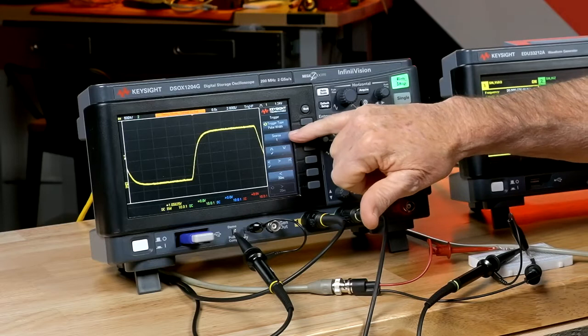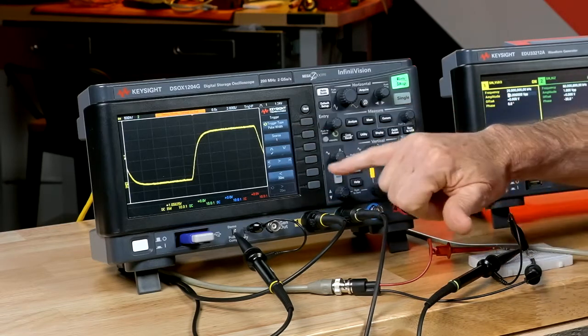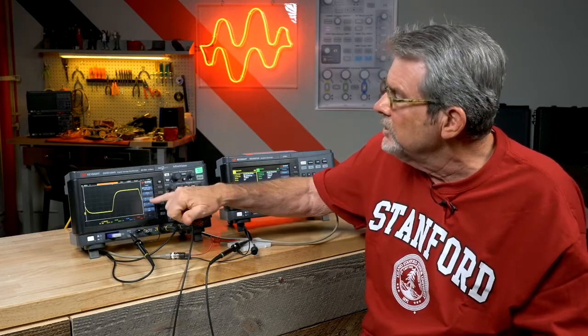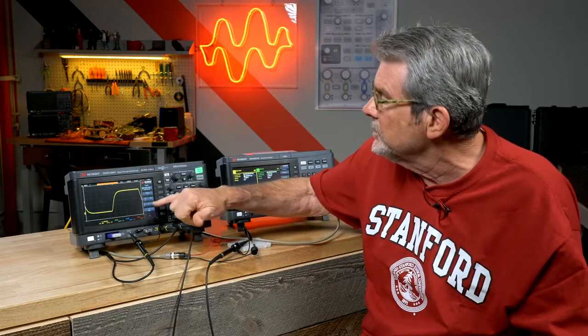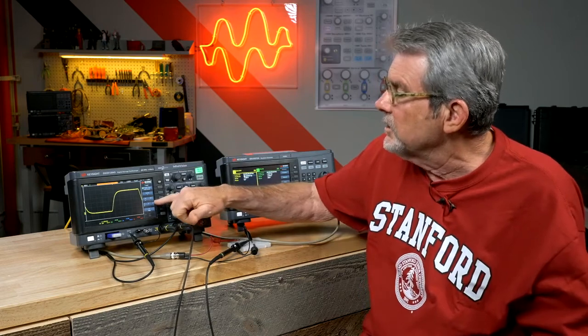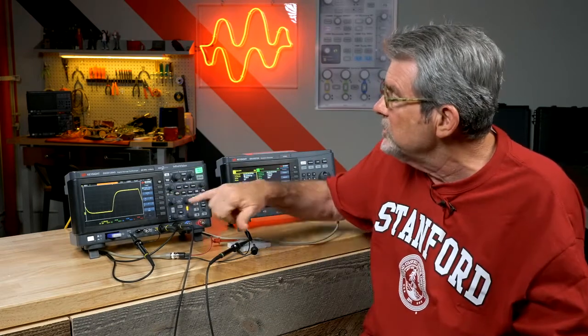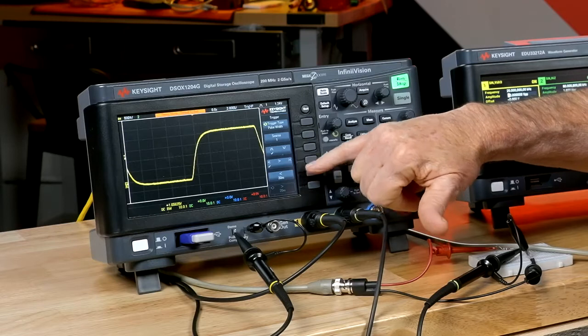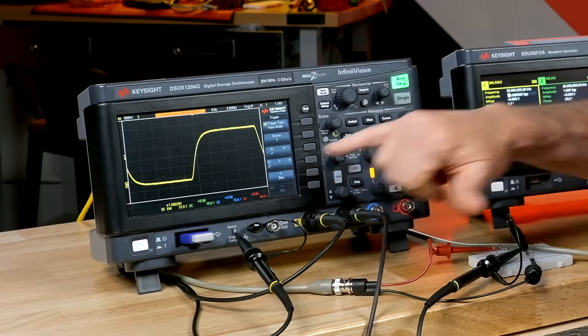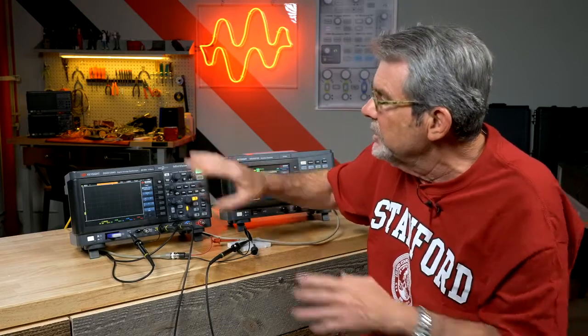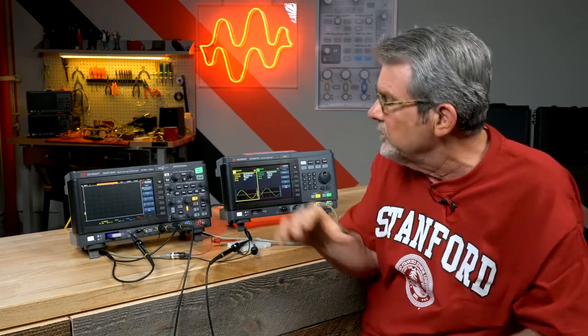So here it says source channel 1, that's the input I'm using. I can say, is it a positive pulse or a positive glitch or a negative? It looks like a positive one to me, so that little icon means positive. And then I can put a time qualifier on it: less than, greater than, or within a range, and then the specific time. Right now it says a positive pulse for less than 30 nanoseconds. So right now the scope is not triggering. If I clear screen, you see nothing, because it's looking for a pulse narrower than 30 nanoseconds.